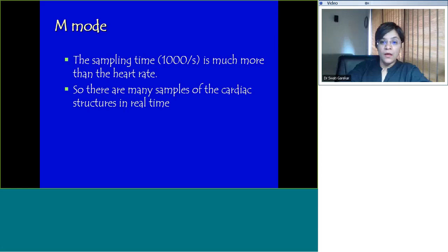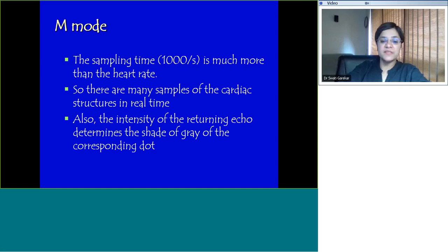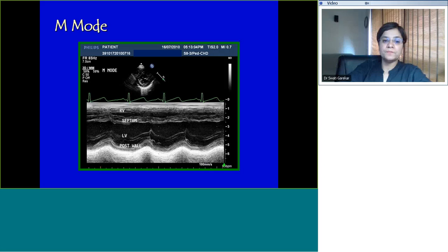In this cartoon, on the y-axis you have distance from the transducer. Here's your probe, the chest wall, sound waves hitting through the various heart structures. A millisecond later you have another sound wave going through the same bit of the heart. On the x-axis you have time. What it's telling you is what happens when you keep on interrogating the same slice of the heart over time and you display it in this format. Because our sampling rate, around thousand per second, is much more than the heart rate, there are many samples of cardiac structures in real time. The second aspect is the gray scale. How intense the returning echo is determines the shade of gray of the corresponding dot.